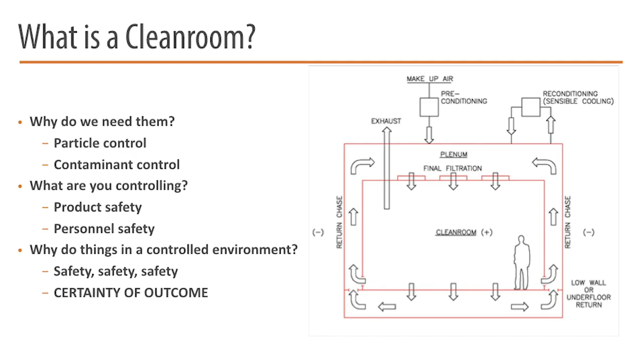So what's cleaner, an operating room or a clean room? Anybody want to hazard a guess? You're wrong, it's a clean room. Operating rooms operate at a level of about ISO 7, and we'll get into that, Brad will explain it well. Clean rooms obviously go up to, or down to, ISO 5, and so on.